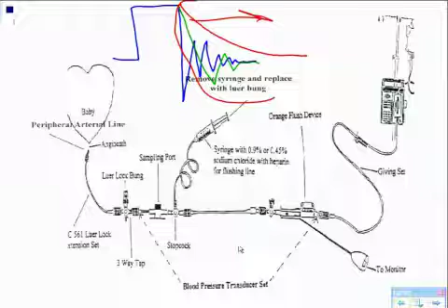Okay? If you see that if you squeeze the line and it only goes up to 100 and it drops back down, or barely you can see the difference between the A line, and what happens is that's the problem with you didn't do enough pressure on your actual pressure bag. You didn't set it up to 300. You forgot to pressurize it. Or if you pressurized it, but you turned the stopcock the wrong way and the air bled out, which happens to all of us, okay?